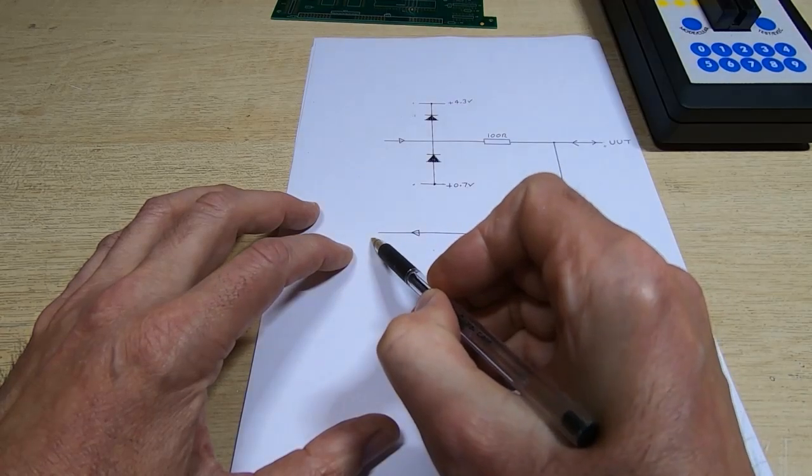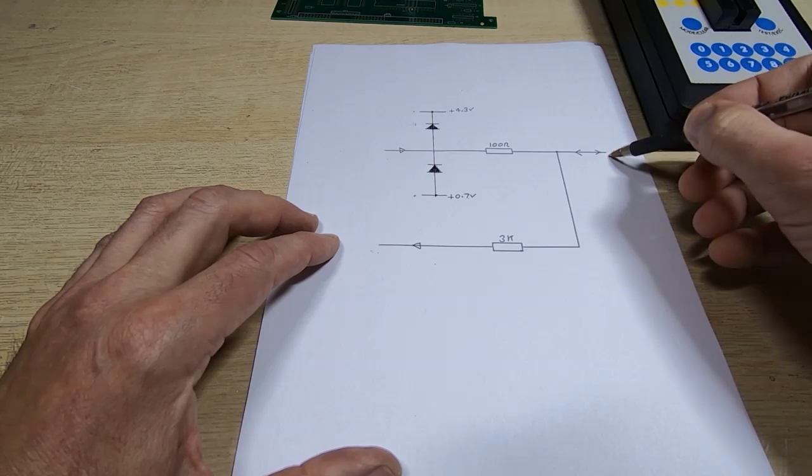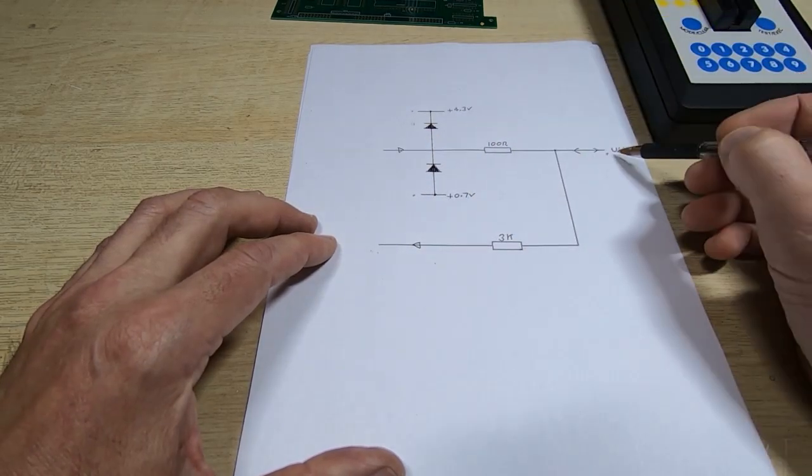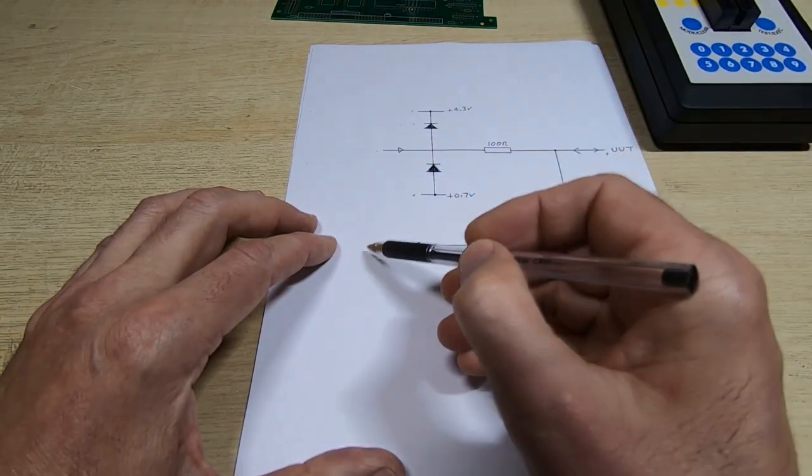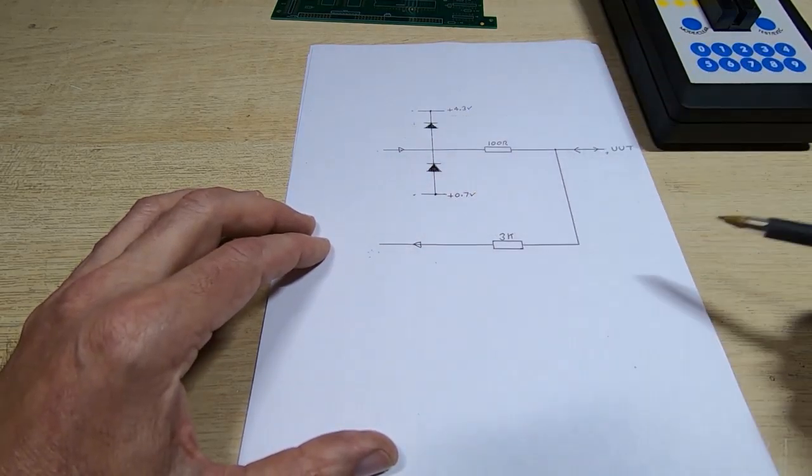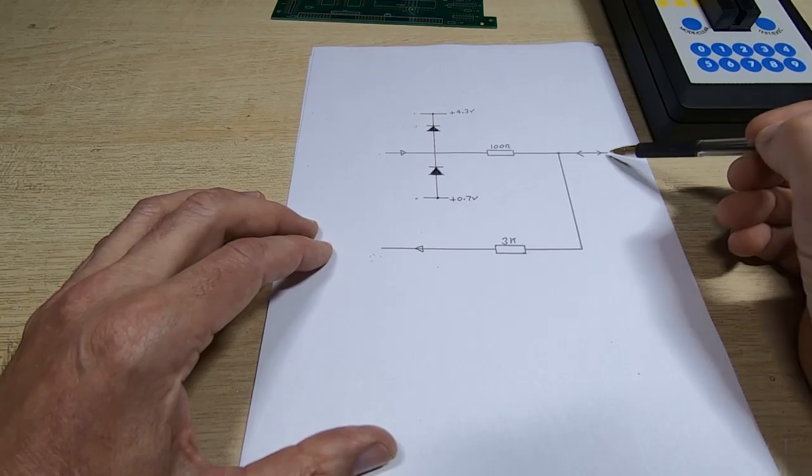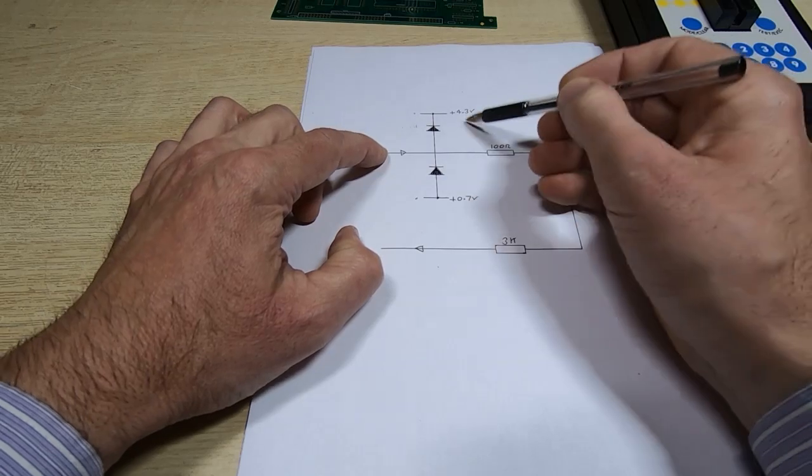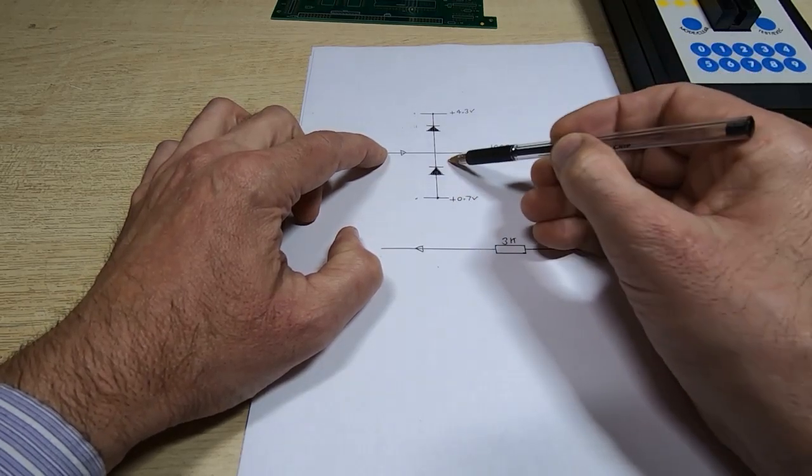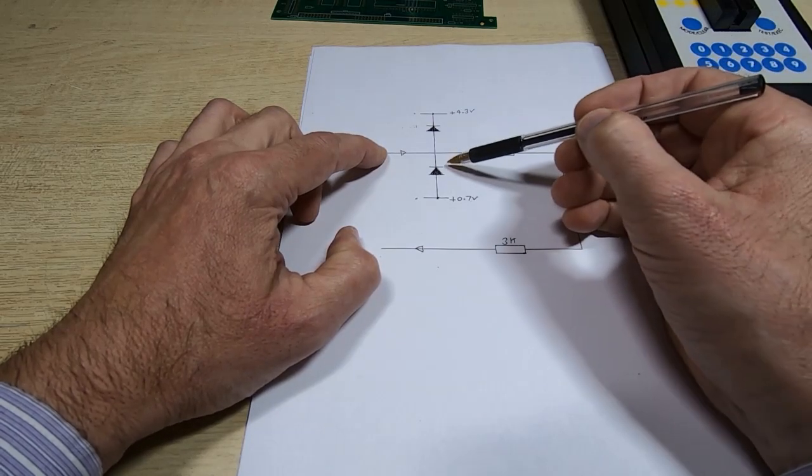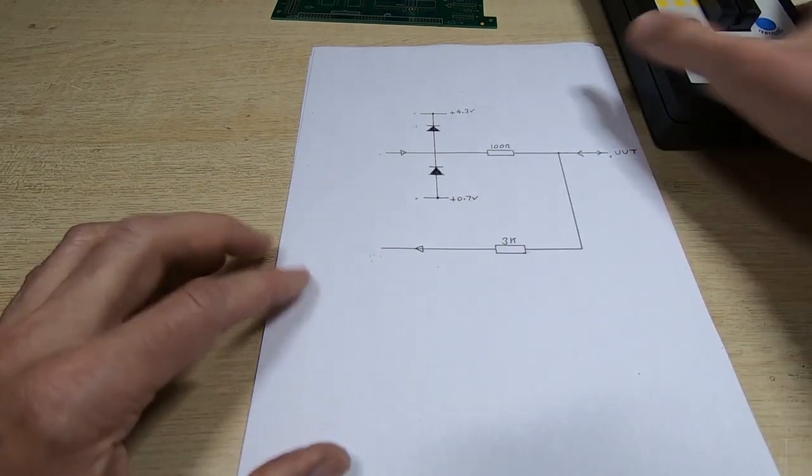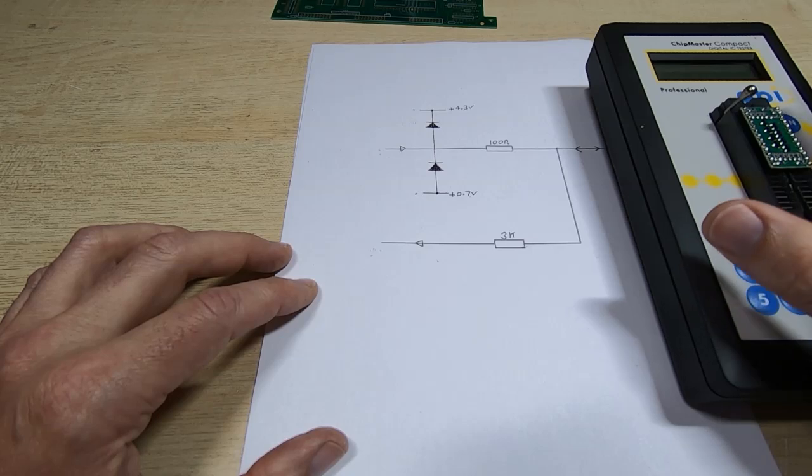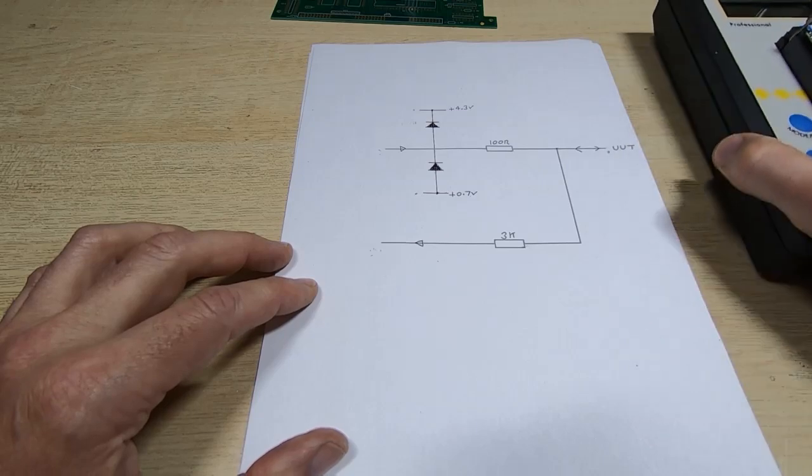It applies an output and measures the voltage at multiple points. It doesn't put a load on the input, so you should get TTL level voltages. It then does the reverse, toggling between low and high at each end, monitoring these points. This picks up any missing devices or shorts. It then toggles these values to make sure it can pass current through the diodes and does the reverse to ensure the diodes don't pass current the wrong way.